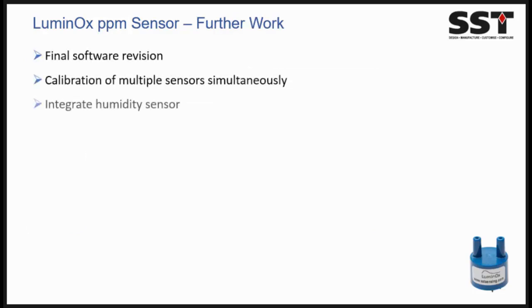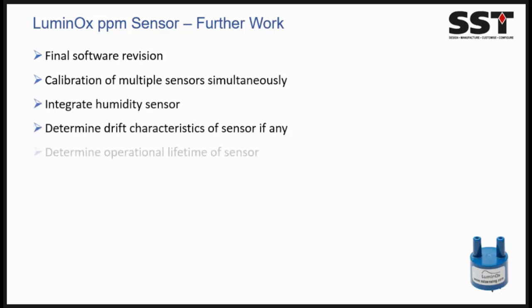So for the work, we are just looking at doing some final software revision to actually give us the Torr value to correlate with an actual O2 reading. Looking at calibrating the sensors, multiple sensors. So we're looking to calibrate around 400 sensors simultaneously. We're looking at integrating a humidity sensor. The formulation is virtually identical to what we have just now. So we know that from 0 to 99% relative humidity, as long as it's non-condensing, there's no effect on the sensor itself. But we're looking to add a humidity sensor as customers have been looking for that.